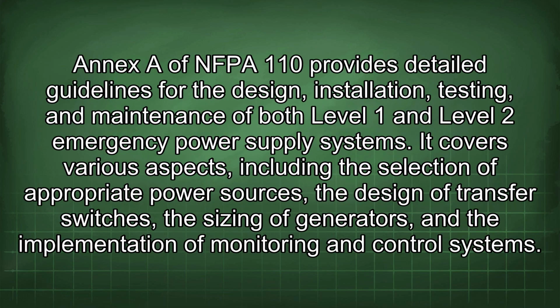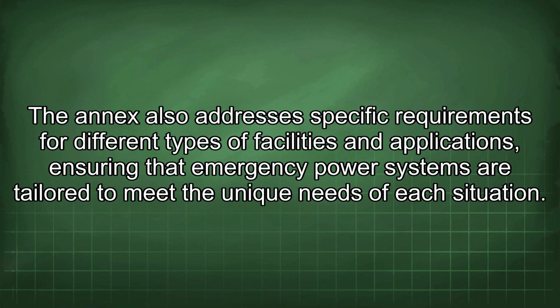Annex A of NFPA 110 provides detailed guidelines for the design, installation, testing, and maintenance of both Level 1 and Level 2 emergency power supply systems. It covers various aspects, including the selection of appropriate power sources, the design of transfer switches, the sizing of generators, and the implementation of monitoring and control systems. The Annex also addresses specific requirements for different types of facilities and applications, ensuring that emergency power systems are tailored to meet the unique needs of each situation.